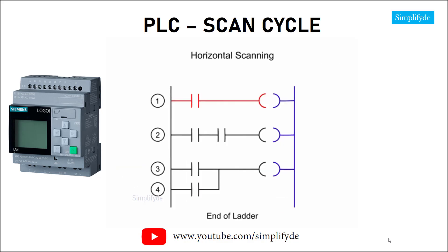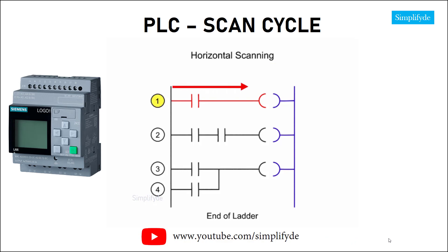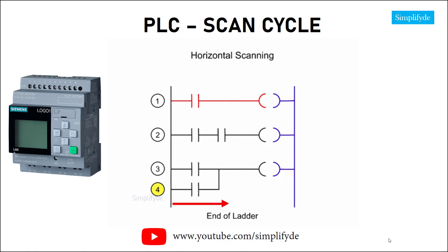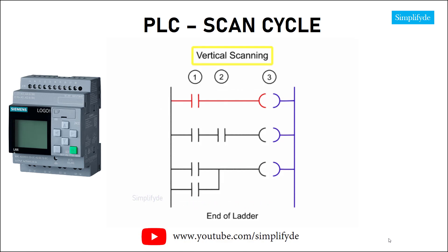The output status is updated with the light changing state from OFF to ON as defined in the ladder logic. The PLC scan follows a specific pattern to execute the program. The first pattern is referenced as horizontal scanning, where the program is examined from the first command, left to right across the rung, and top to bottom. Vertical scanning, on the other hand, examines the input and output instructions from the first command, vertically, column by column, and left to right.